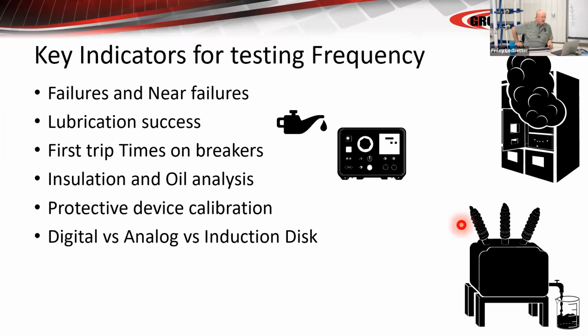So when you go out and test a big bunch of breakers at a petrochem plant, we typically see 12 to 15% of the breakers that would not have successfully interrupted a fault or protected a piece of equipment or a person. 12 to 15%, depending upon the manufacturer. That's at a less than 5 year maintenance interval.